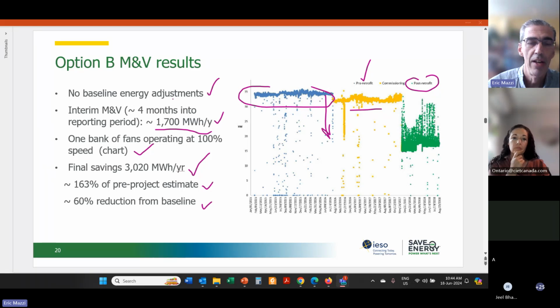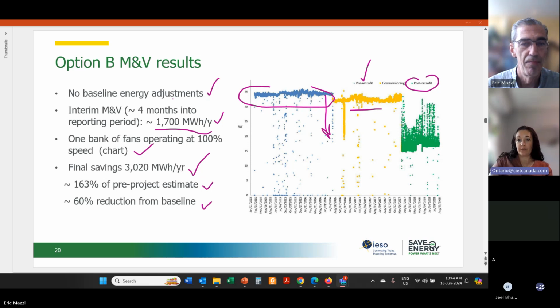There was no need to adjust the energy for outdoor air temperature, because that was not a variable that directly affected the ventilation settings. It was about occupancy, and there was either very little change, or there was just no data available. So that's the basics there. Great, thank you. One of the other questions was, please elaborate why there was no adjustment required to the baseline. And I think you just answered that as well.